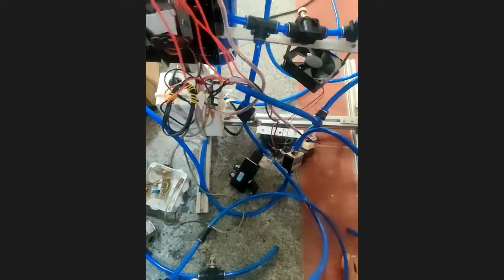So it looks like the RO canister might not be a good way to go. Yeah, exactly, that's what I think so. Because as per the Jamboard created by Abhimanyu, and you guys have added to it, I see that most of those who got 95 plus percentage, I'm getting a similar rating. I'm getting like 2.5 bar per sieve, all that is working, but I'm still only getting 70%. So I suspect this leak to be a major cause of that, is what I think. But if guys can suggest something...